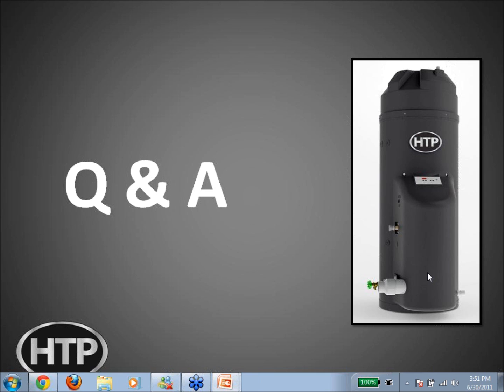What is the minimum GPM flow required for the flat plate heat exchanger to fire up? Paul, the minimum flow rate is 0.5 gallons per minute, which is pretty much standard with all tankless heaters. The specification is in the manual, and the flow switch activates at 0.5 gallons per minute. Once you get over 8 gallons a minute, you will have some velocity noise through the valve, but it's not really that bad unless you're right next to the appliance. It was a concern, but once you start getting over 8 gallons a minute, you're really going over the capacity of the system to transfer the energy required to satisfy the demand.